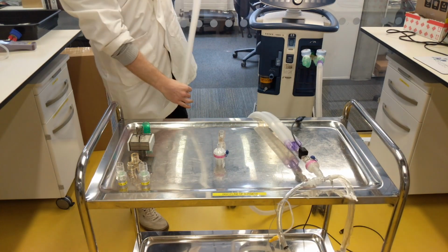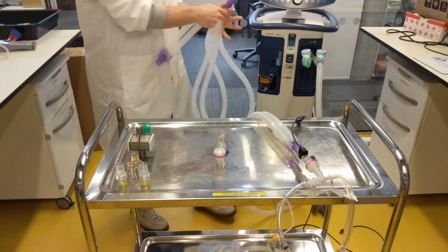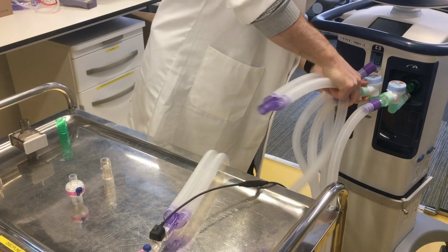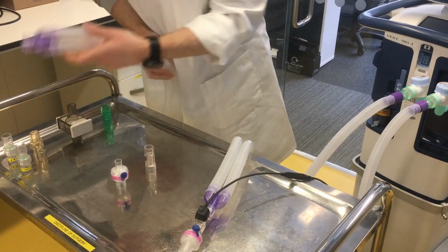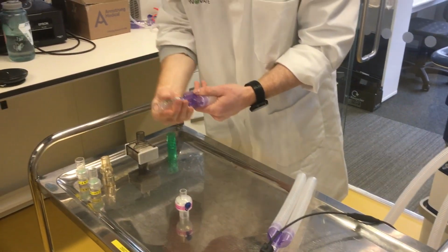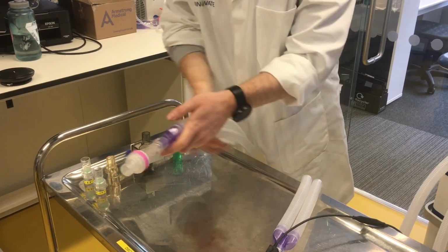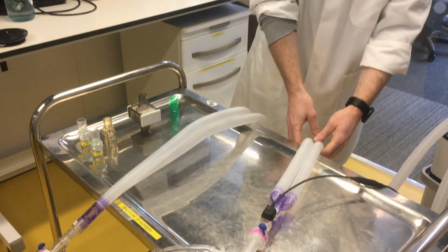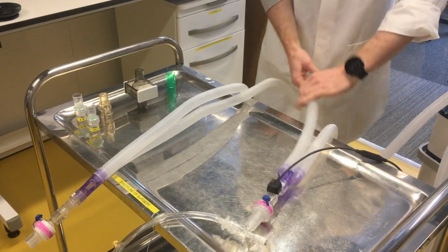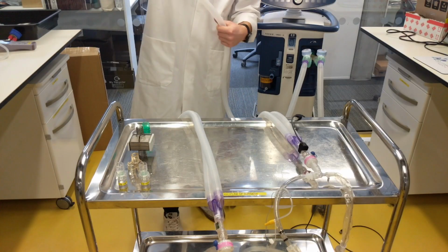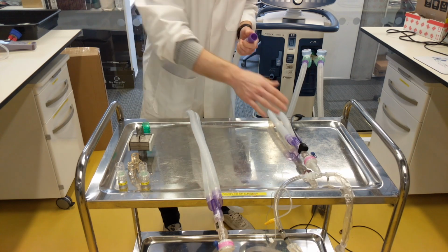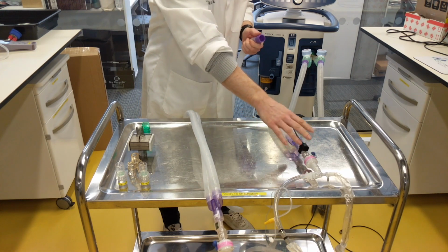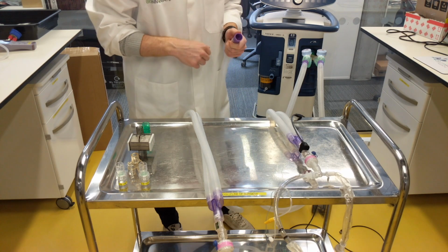So again, we have our second breathing circuit, and we will have our inspiratory limb attached just post the APL valve here. Again, we will run that through our flow meter and the HME. Now if we come on to the expiratory side, in order for the APL valve to function properly and effectively reduce the tidal volume and pressure for this patient, we need to ensure that the line can't backfill through the expiratory line.